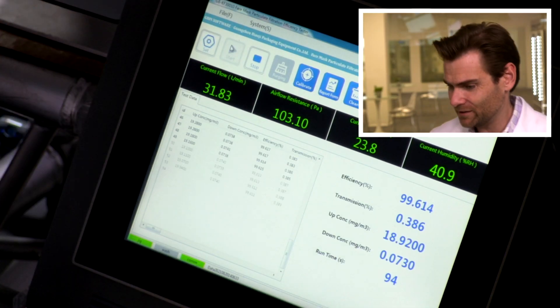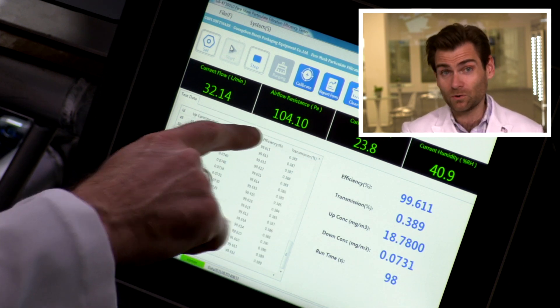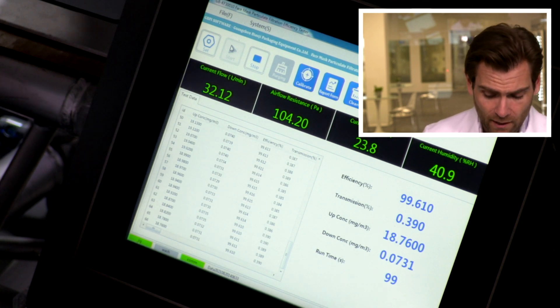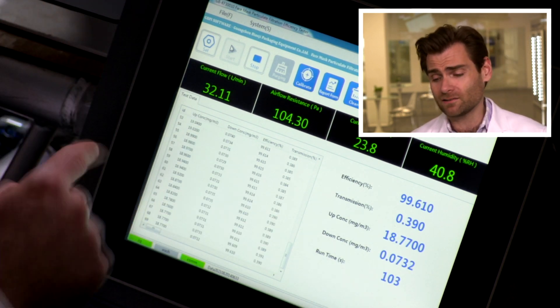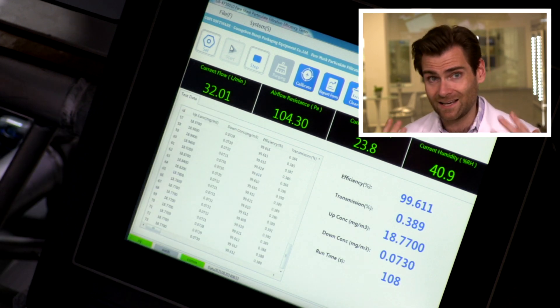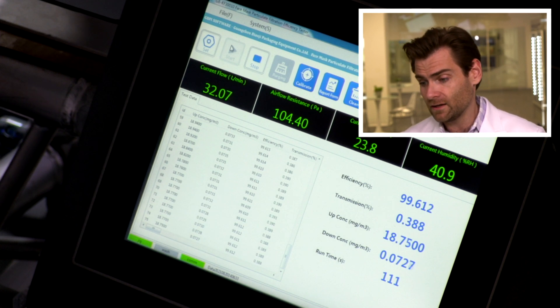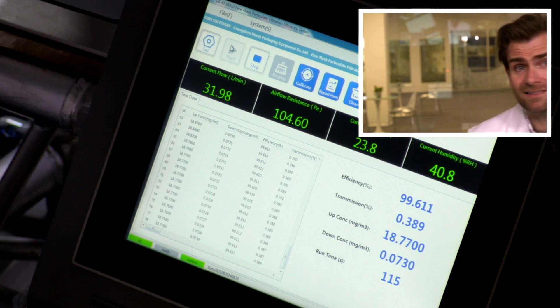All right, let's switch over to the PFE machine to see how we're doing. Look at this — airflow resistance is 103, which is insane. We've seen that before; I tested the Indiana face mask, also an American-made mask, and they were sub-100 with their flat-fold design, or KN95 design as I call it. Great efficiency — great fabric. This machine tests just the fabric, not the fit.